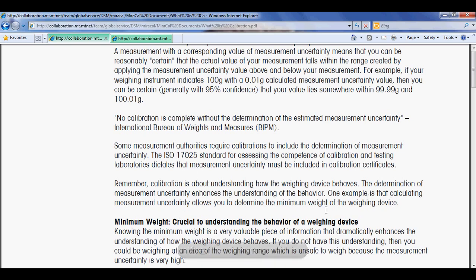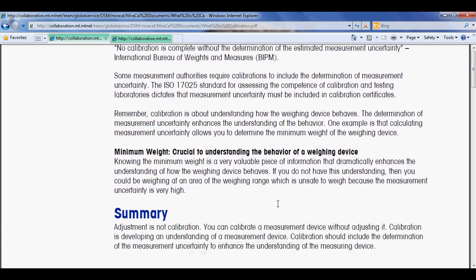One example is that calculating measurement uncertainty allows you to determine the minimum weight of the weighing device. Now, if you've done any calibrations recently, you should have been educated, you should be trained on knowing what minimum weight is. And minimum weight is crucial to understanding the behavior of a weighing device. So knowing the minimum weight is a very valuable piece of information that dramatically enhances the understanding of how the weighing device behaves. If you do not have this understanding, then you could be weighing at an area of the weighing range which is unsafe to weigh because the measurement uncertainty is too high.